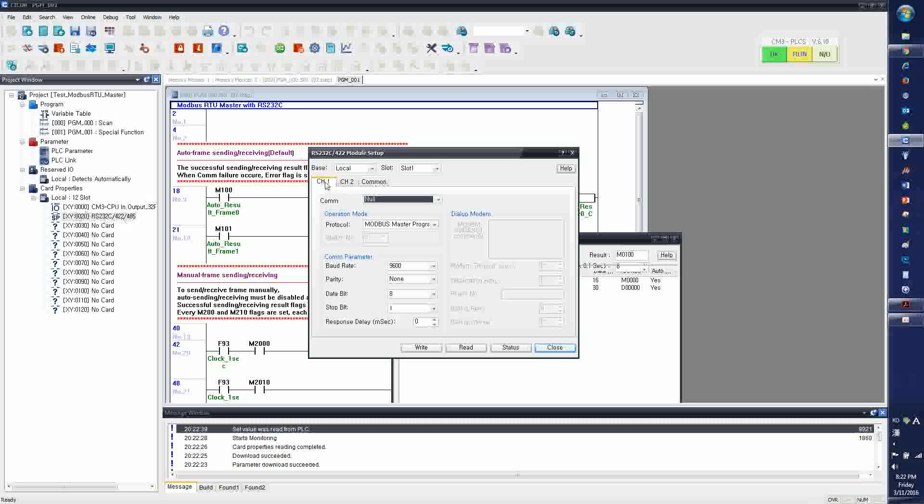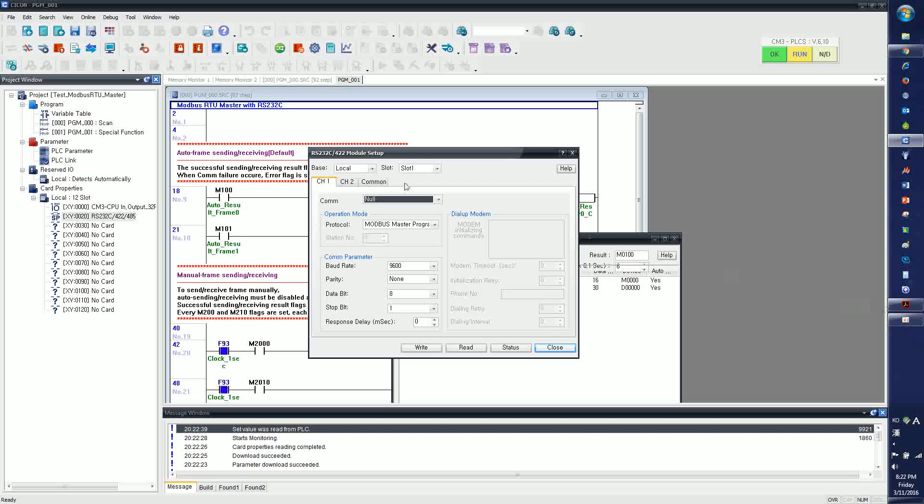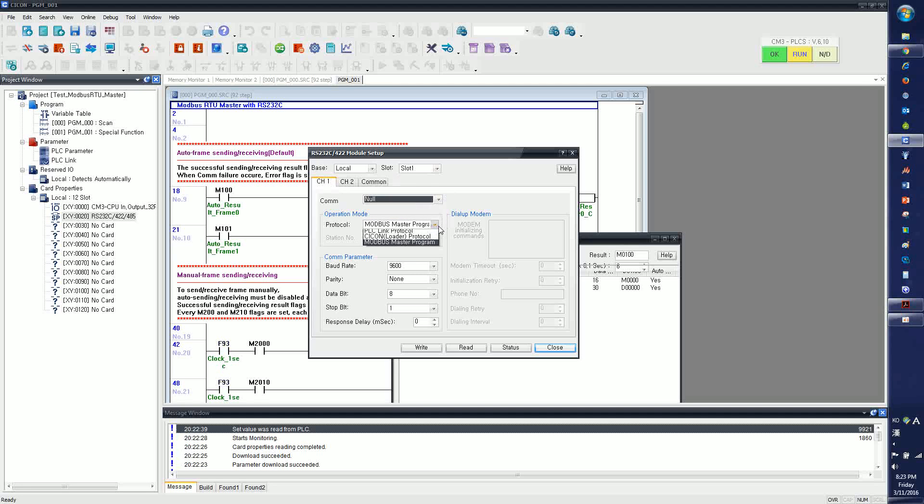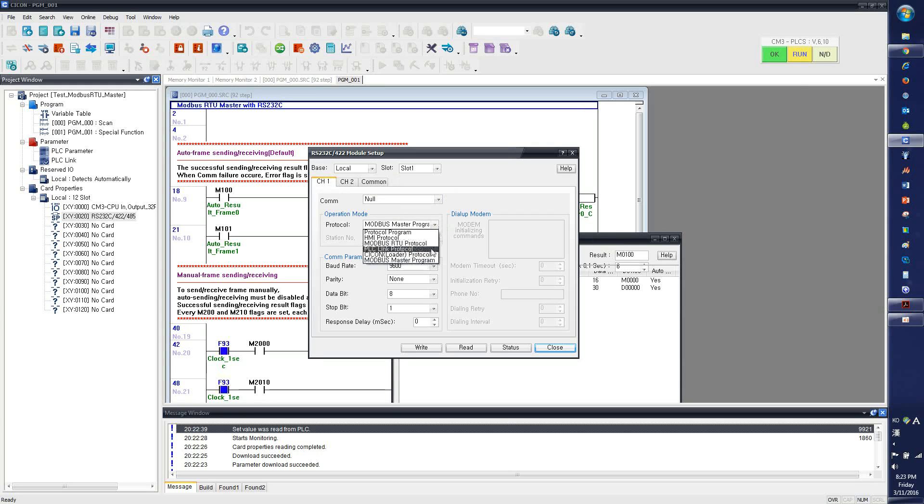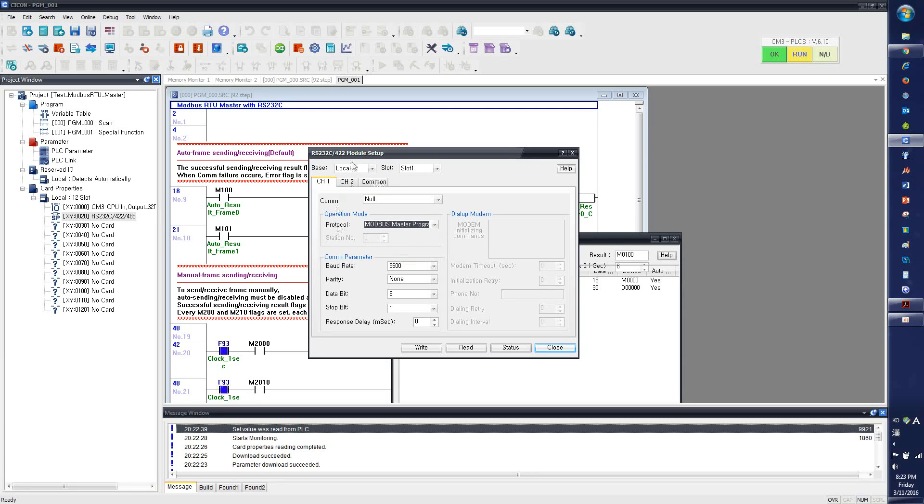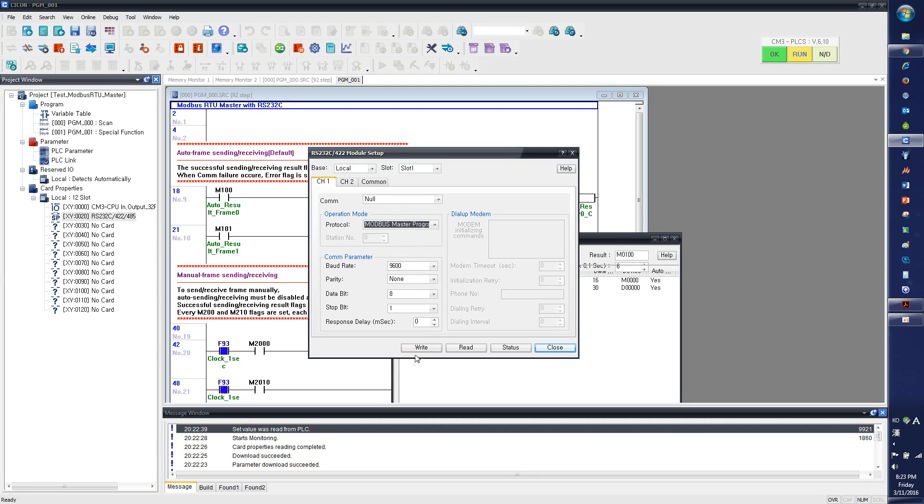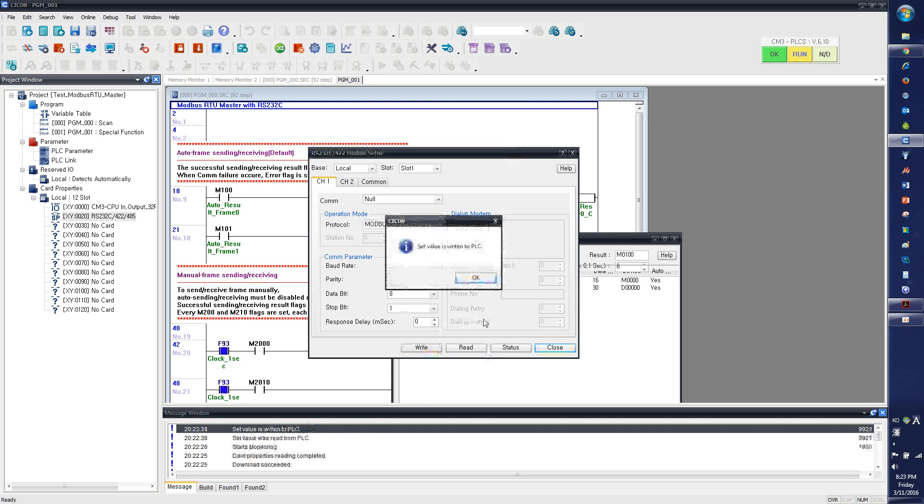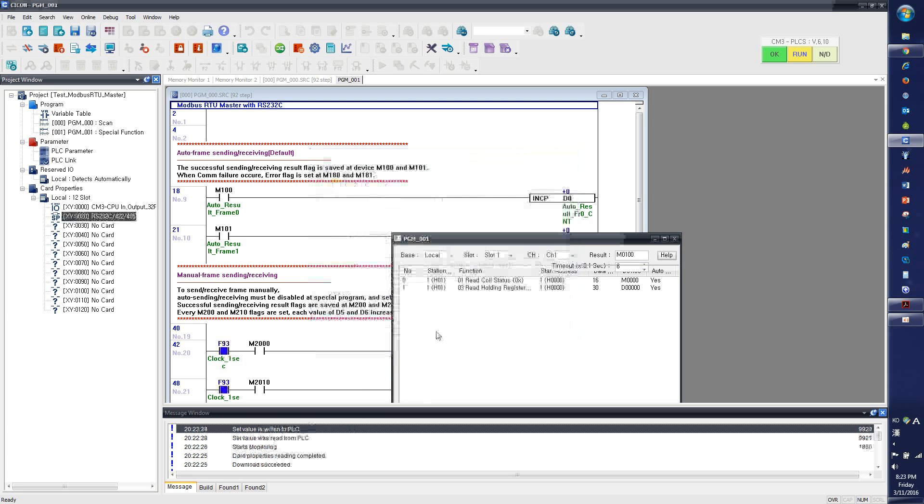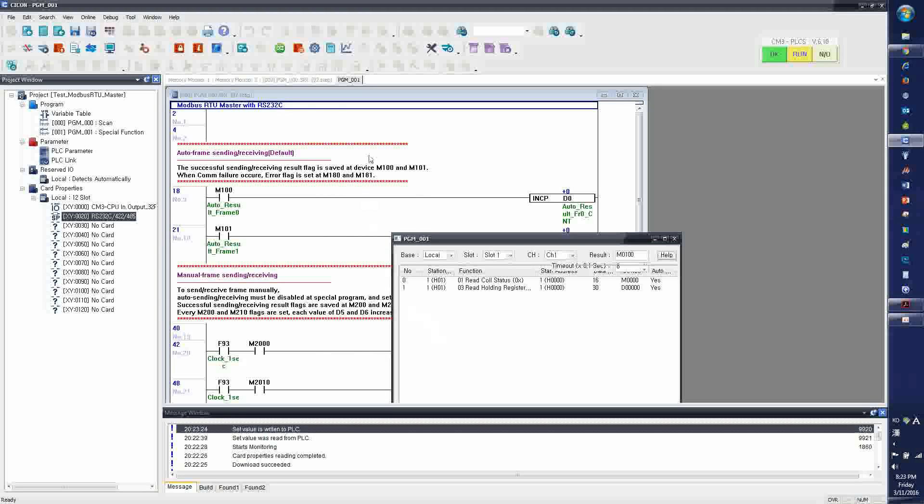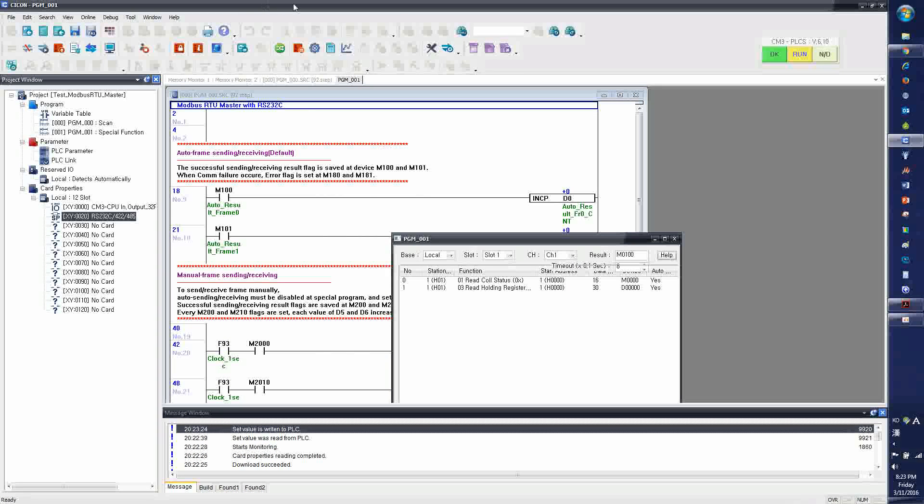Now you want to configure the serial module, which is the master communication parameter. So I'm using the channel one, which is local base, slot one. Channel one, communication is null. And it is Modbus master program. My serial module is my Modbus master. And the baud rate, I'm going to leave it as the default settings. And I'm going to write it. So now I have the Modbus RTU master is ready.